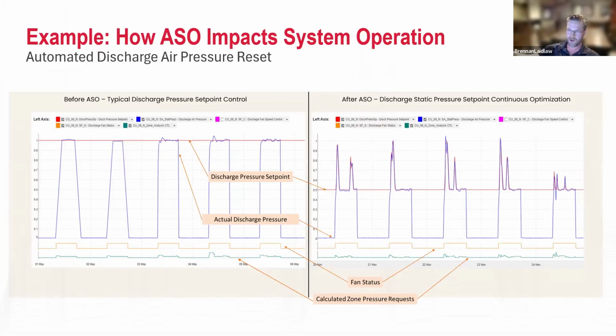And this is an example of how an automated system can apply known principles like ASHRAE's Guideline 36, which is called trim and respond controls. It'll look at all the zones in the building, and it'll determine whether it needs more or less airflow. So it can bump the set points up and down.